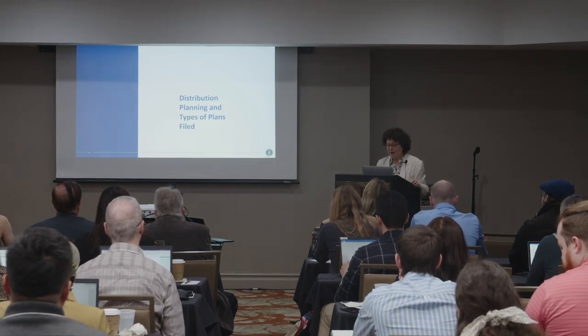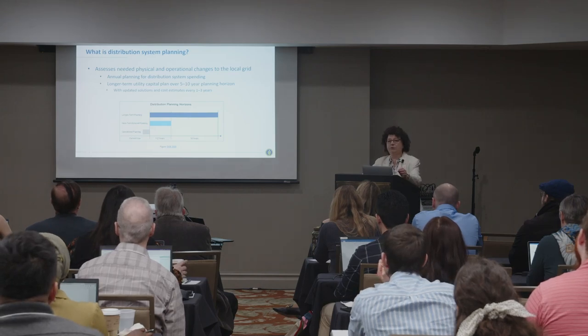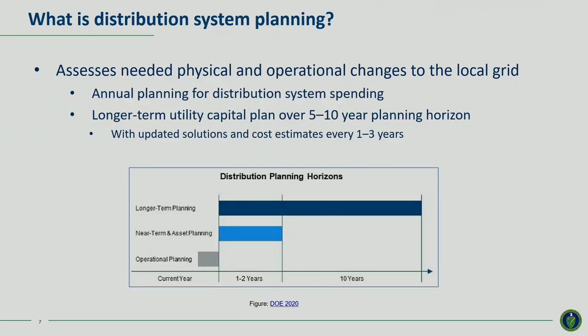So what is distribution planning, and what kinds of plans are regulated utilities required to file? Distribution planning assesses the physical and operational changes needed to meet the needs for safe and reliable service. At its core, it's typically an annual process that the utility runs with a one to two year time frame, but there's also a longer-term capital plan because some investments, like substations, take a long time to plan — at least six years — to get the equipment and build a facility. Utilities have done distribution planning since they first began operating electricity systems.